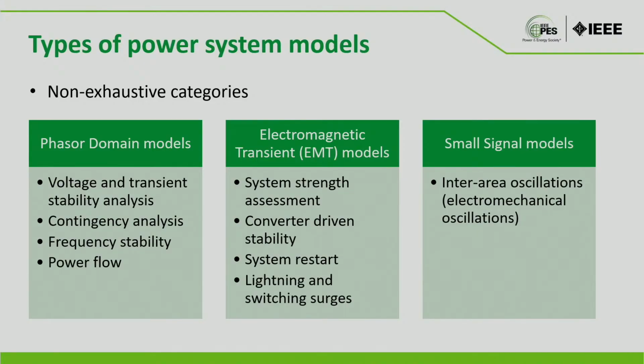The second category is the electromagnetic transient model. Quite a few system operators are now using electromagnetic transient models for system strength assessment, looking at the interaction between the IBR and the grid, or between IBR and IBR. That forms part of converter-driven stability.